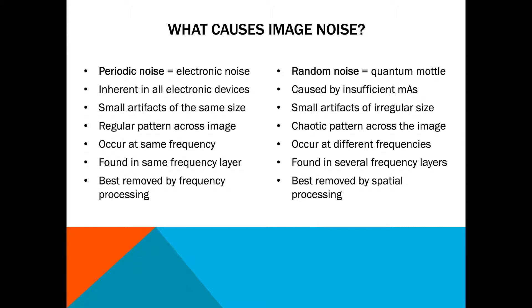Random noise is what the name implies — it's quantum mottle. It's caused typically by not enough mAs; if the kVp is too low, that can also cause it. It's still small artifacts, but they're of irregular size because it's picking up noise based on patient size. It's a chaotic pattern across the image, occurs at different frequencies, and is found throughout the frequency layers. So that makes it more difficult to remove using frequency processing — it's best removed by a spatial domain processing operation, which is pixel location specific.